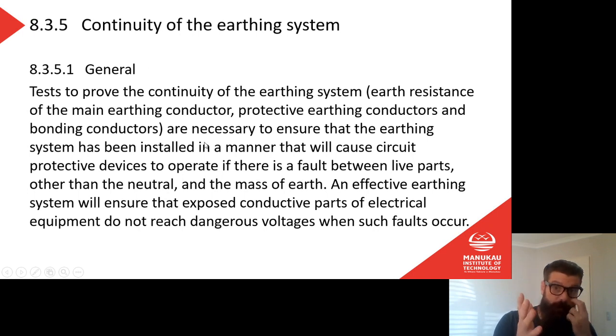So as I just said about the earthing system, we need to test the continuity. Tests to prove the continuity, that is a continuous wire from one end to the other, of the earthing system are necessary to ensure the earthing system has been installed in a manner that it will cause circuit protective devices, that's our fuses and circuit breakers, to operate if there is a fault between live parts other than the neutral and the mass of earth. An effective earthing system will ensure that exposed conductive parts of electrical equipment do not reach dangerous voltage when such faults occur. Again, I'm not going to get into the detail of what all of that means.